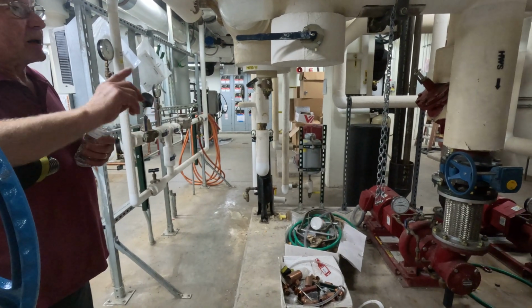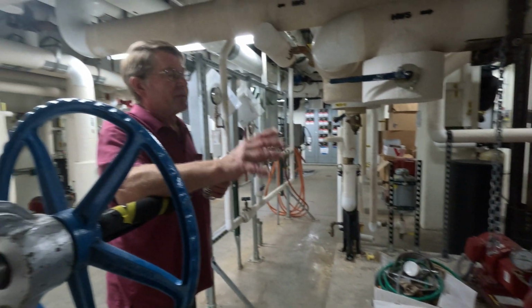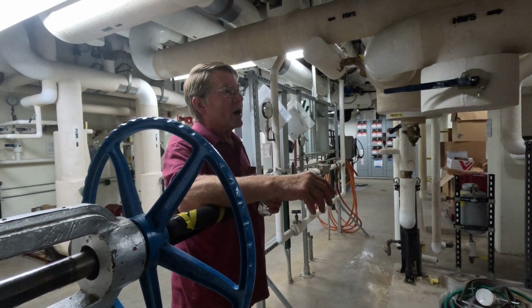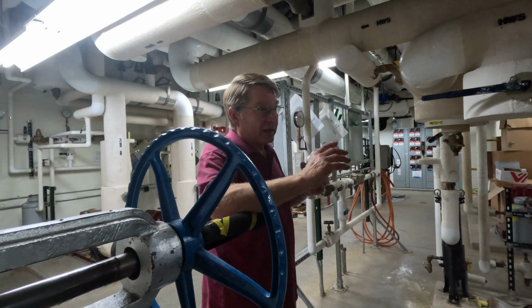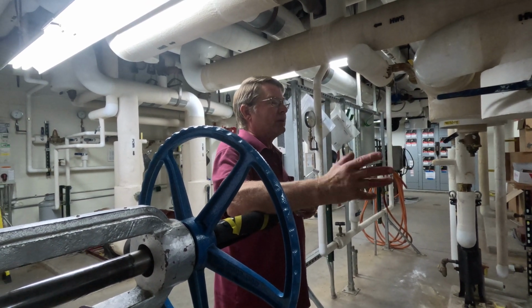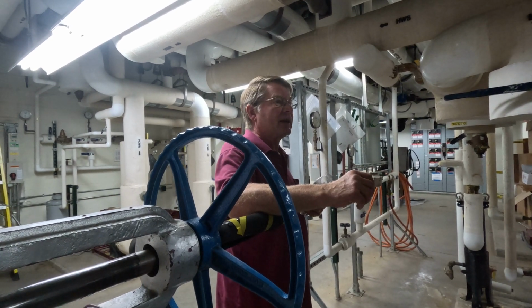Now, we're talking about Engineering Hall and their reheat system. Because of the efficiency of this building, compared to a building like Engineering Hall, where the reheat water is at about 180 degrees because it's got to do a larger capacity and has further to travel, our building here being more efficient, we can run it at 120. So again, there's your energy savings with that.